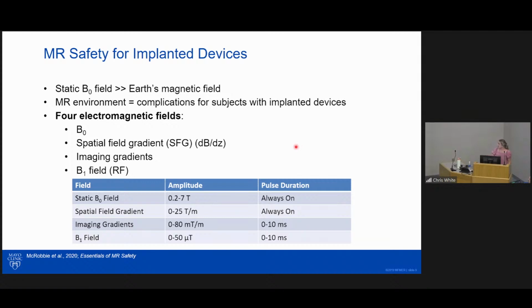And then this table shows the amplitude and pulse durations of these 4 different fields. So note that the static B0 field and the spatial field gradient are always on, meaning that these fields are going to pose a hazard for subjects with implanted devices, regardless if the scanner is running or not.